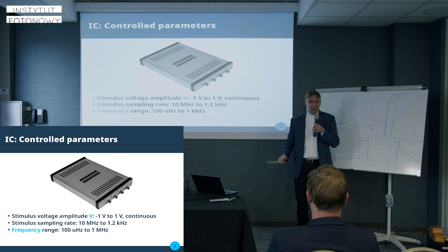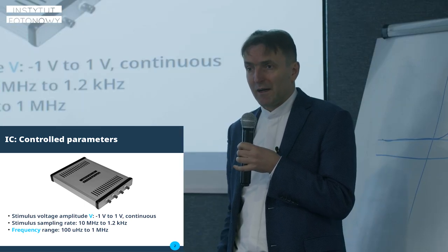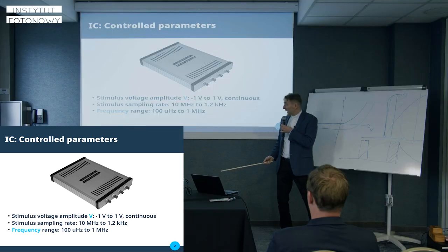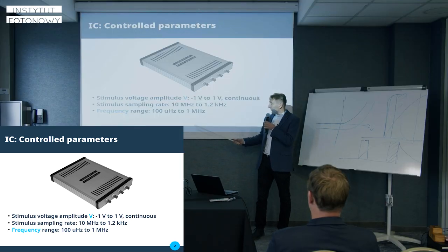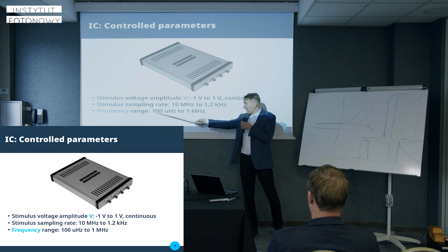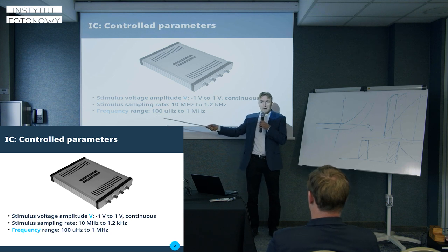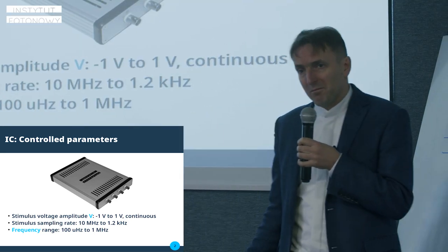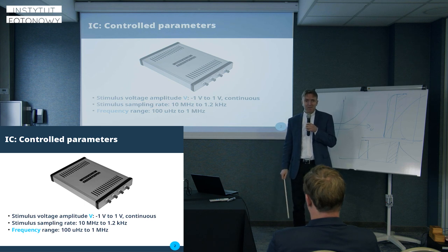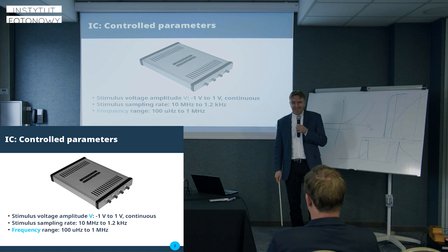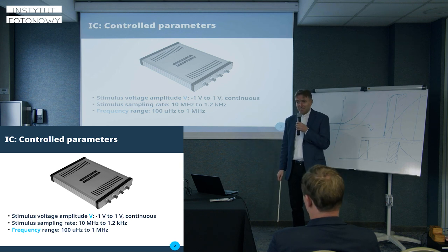However, because we have that many data points, we can reduce noise — so we can have high detectivity of even small changes in the signal. The frequency range is up to one megahertz. It can go down way below, but I don't know if anybody has the patience to wait weeks for one cycle of measurement. One tenth of a millihertz is perhaps a reasonable lower limit, but if somebody needs even lower, there is no hardware limitation — just perhaps the user's patience.